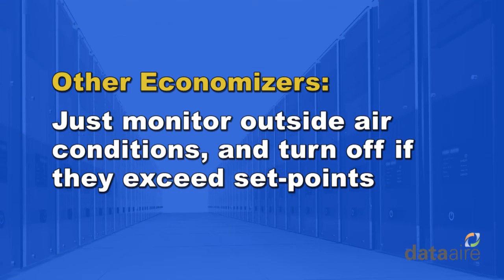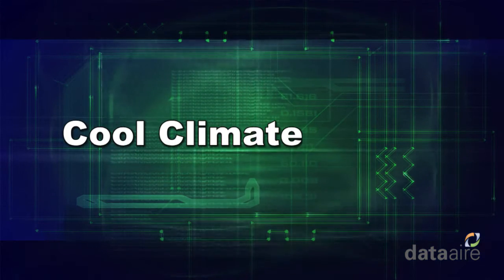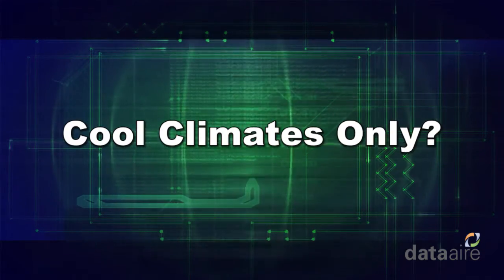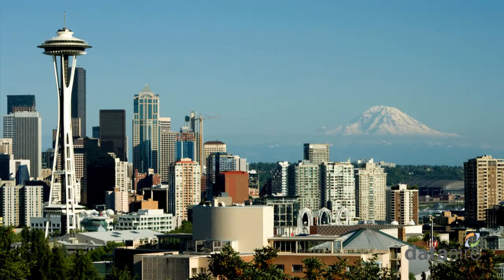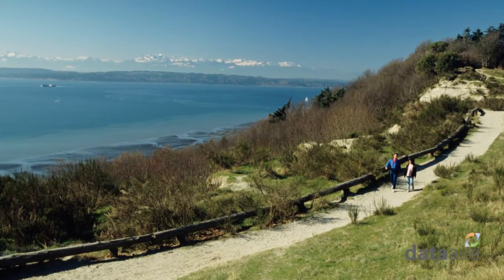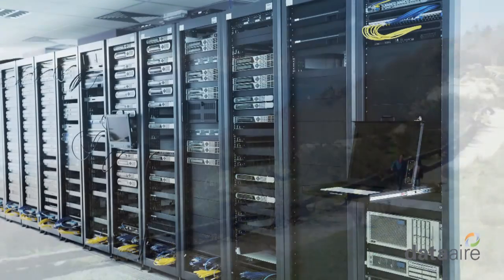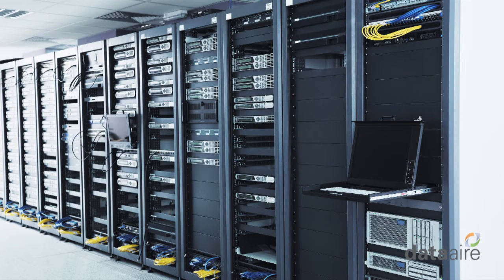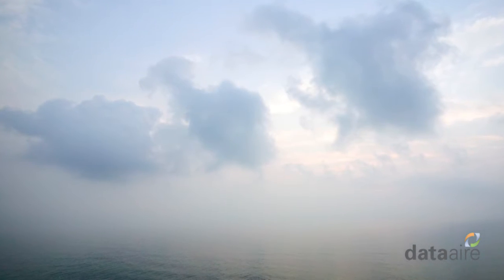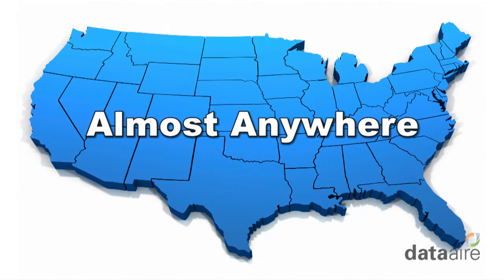Economizers by others merely monitor the outside air conditions, and when they exceed the set points, the economizer is turned off. Some feel that air economizers can only be used in cool climates, typically the northwestern United States. However, with the expanded ASHRAE temperature and humidity envelopes, data centers' year-round cooling requirements, and modulation of actuators, Air Side Economizers can even make sense in hot and humid climates almost anywhere in the U.S.